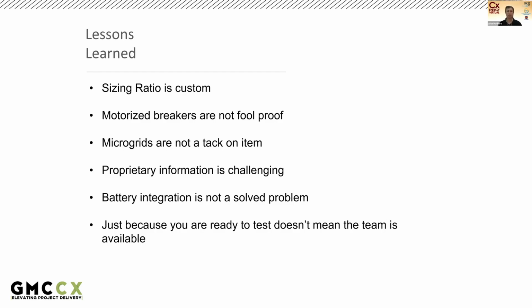Second item is that the motorized breakers, or the remote breakers like CB1 and CB2, are not foolproof. With no mechanical interlock, anyone can click close on the breaker because it's just a controlled interlock. If someone shuts a generator motorized breaker, the breaker will command close and trip right away, and will also trip the generator output breaker.